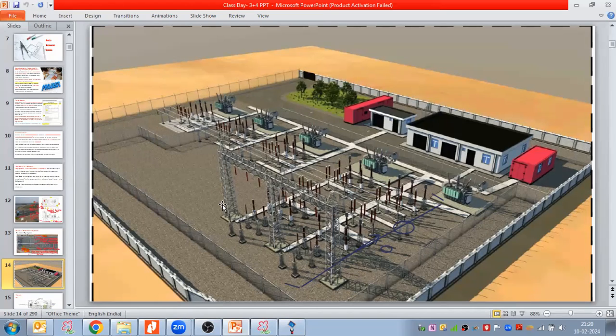This is called the tower, and this is called the beam, and the whole thing is called the gantry or line gantry. This line gantry will provide the connection from the transmission line, and then we will take a drop to the equipment, and through the equipment connect to this common bus bar. And from this common bus bar, again we will take a drop and connect to the transformer.